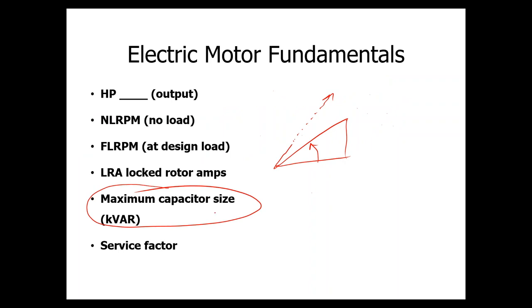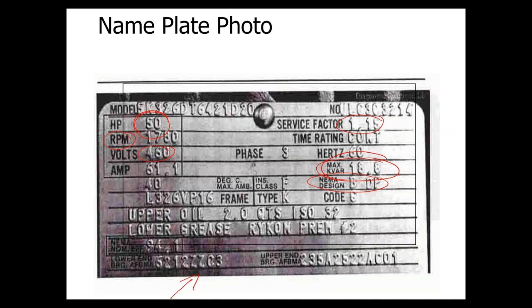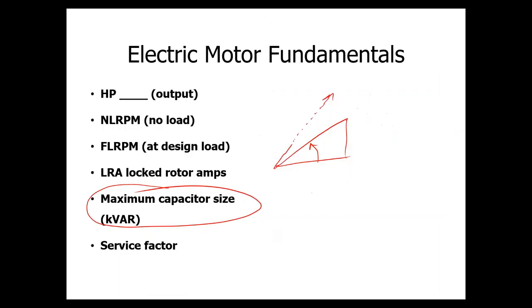What they do in motors is they already know in the lab how much a motor is going to mess up the electric power quality. They tell you on the motor, and you can see this right here, where they're telling you what the maximum size capacitor you would need to put on that motor to correct the power factor back to a reasonable number.